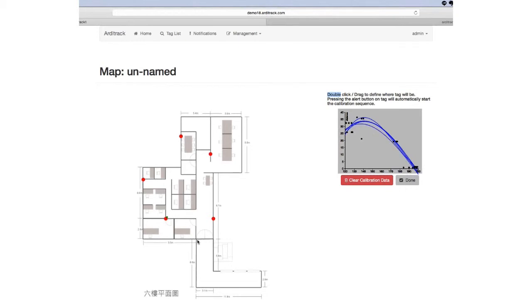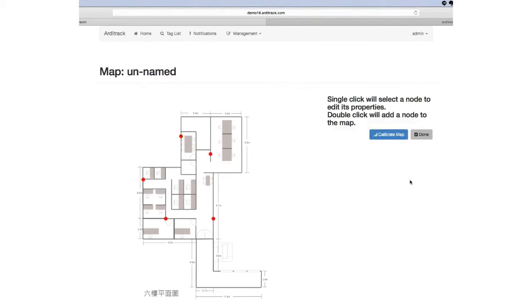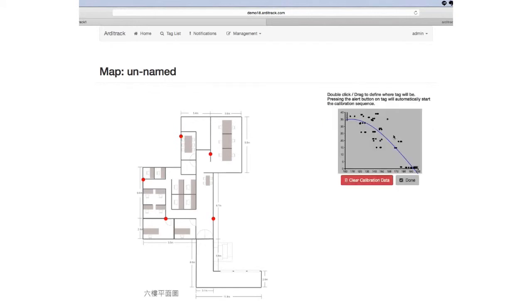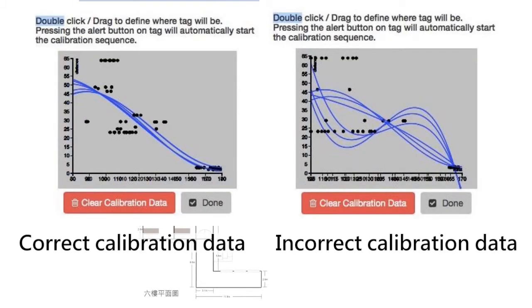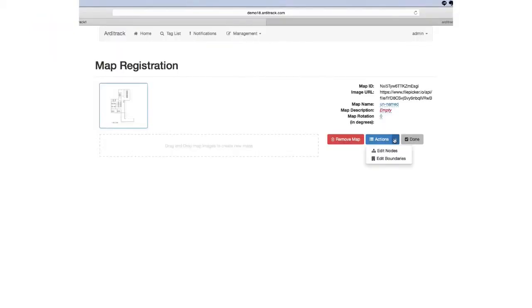If you get a good curve like on the screen, then you can accept it and click done to finish the calibration. If you get an incorrect curve, then you need to delete the calibration data and start over until you find good calibration data. This is the reference. Right hand side is not good data, left hand side is good data.